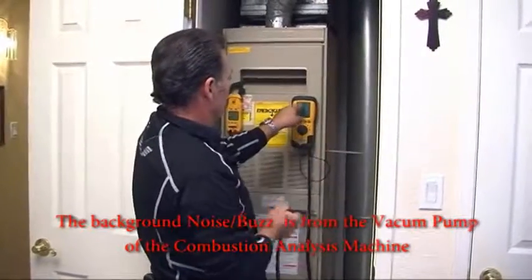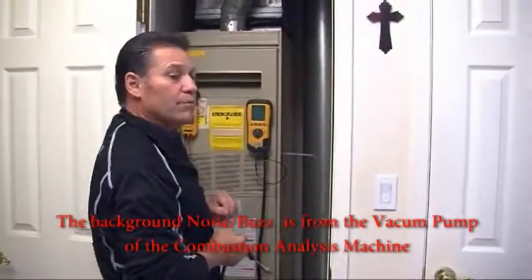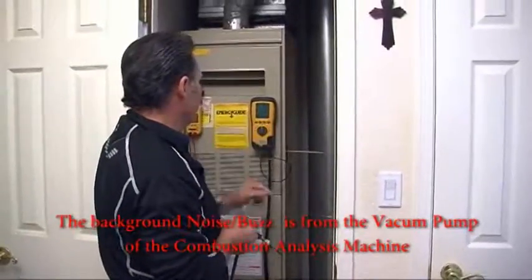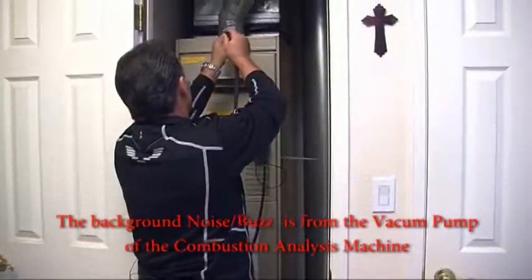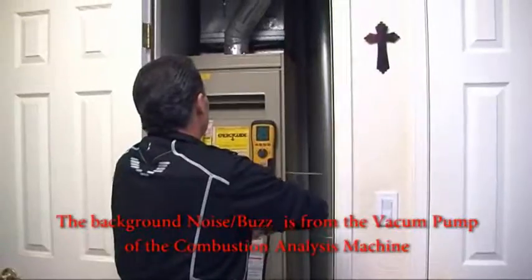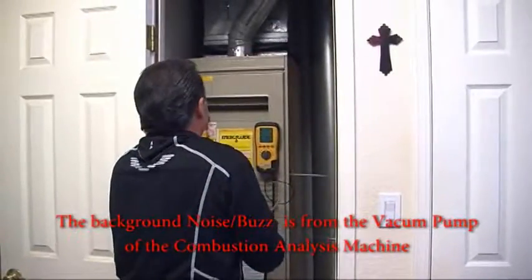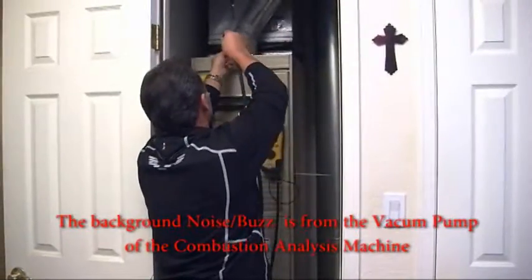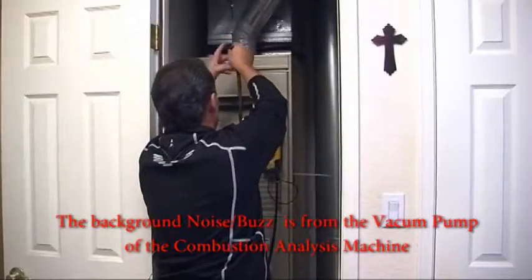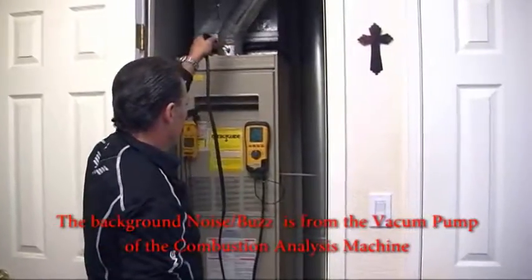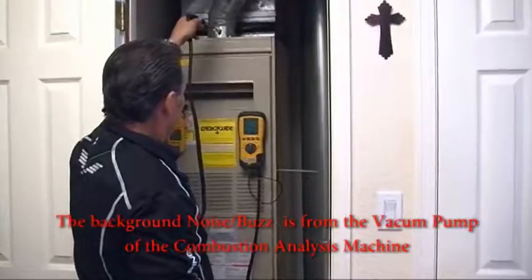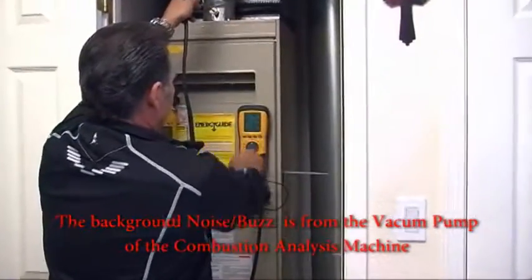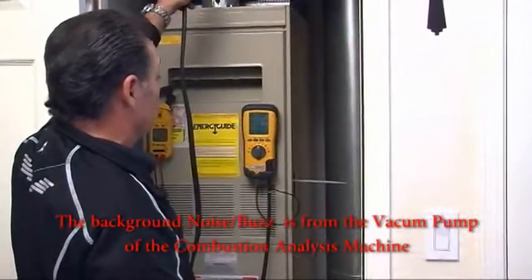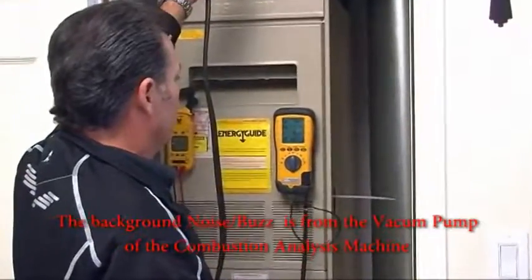We know we're at the reading we need to be before we start our test. We're at 20.9 on our free oxygen. So we're going to go ahead and put the probe in and see what our readings come out to be. Okay? You see the temperature of the flue is going up into the 400s, which is really good. We want to be up at that area.